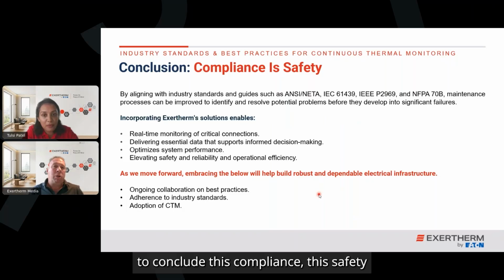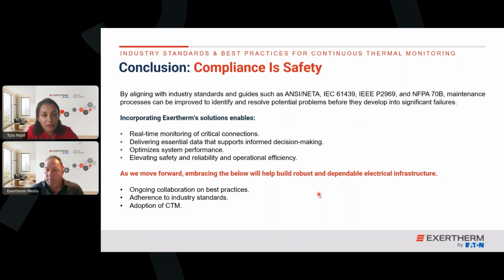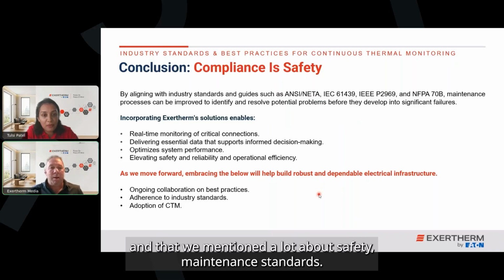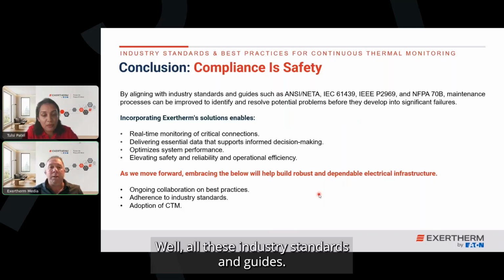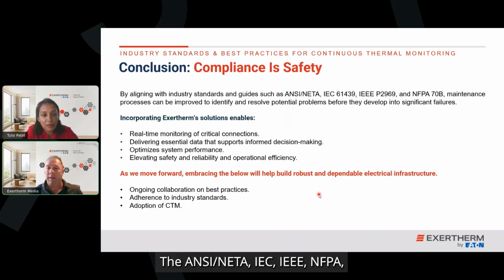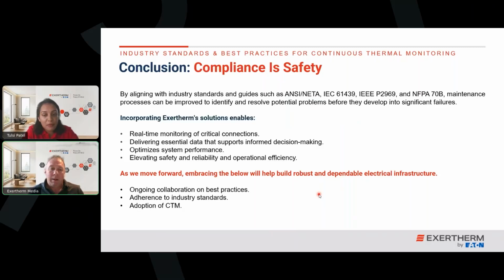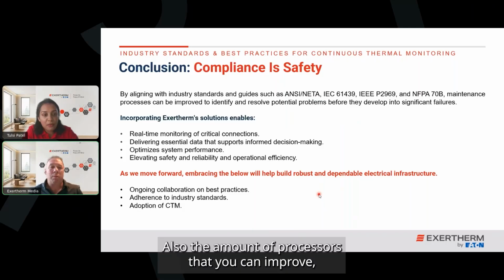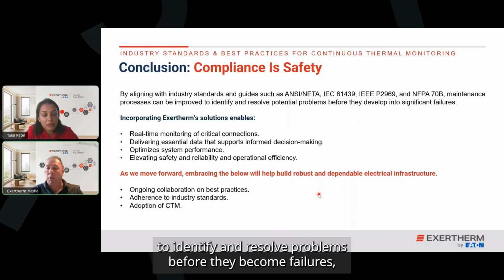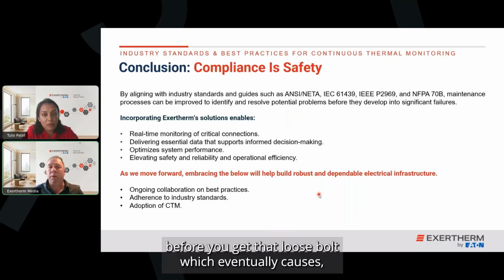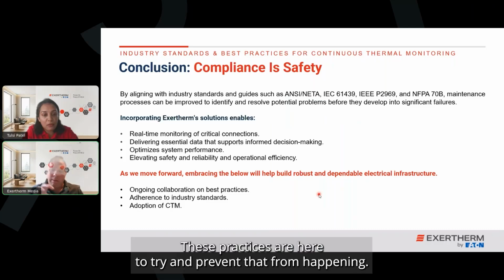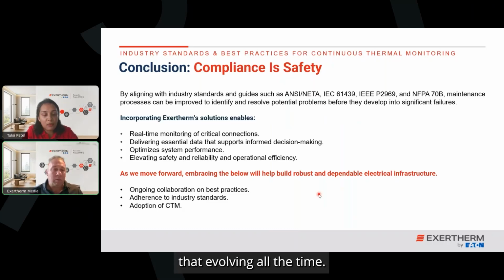But to conclude this, compliance is safety. I know we mentioned a lot about safety, maintenance standards. All these industry standards and guides, be it ANSI, NETA, IEC, IEEE, NFPA, they're all there to increase the safety, the design of the equipment, but also the maintenance processes that you can improve to identify and resolve problems before they become failures, before you get that loose bolt which eventually causes an arc flash and an outage. These practices are here to try and prevent that from happening, and they're evolving all the time.